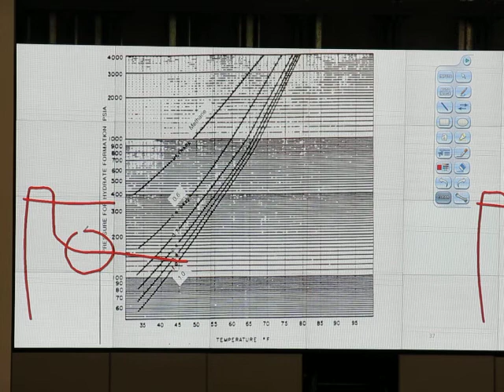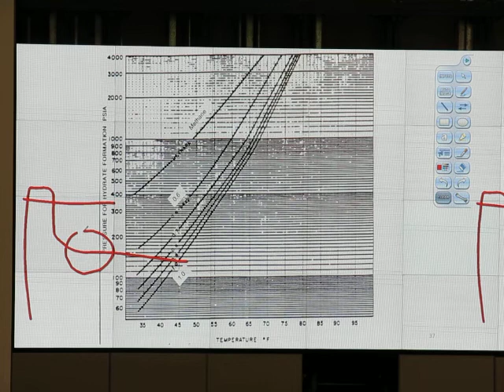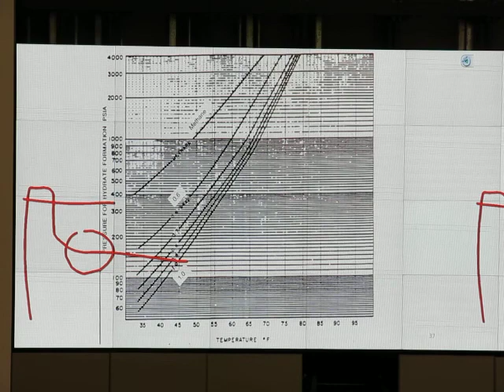So the pressure from the reservoir, it will be hot. So we have reservoir hot gas coming up, but at the surface during the winter it can be cold. When it's cold, the temperature inside the pipe, the outside may be, let's say we have a buried pipe. The pipe is buried underground. So outside we may have ice, but temperature over there may be like 40 Fahrenheit. No ice forming. But even 40 Fahrenheit with the buried pipe, we may have hydrate if pressure is high enough. Okay? If pressure is high enough.